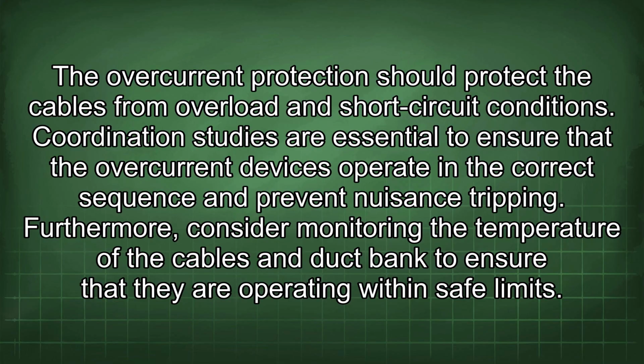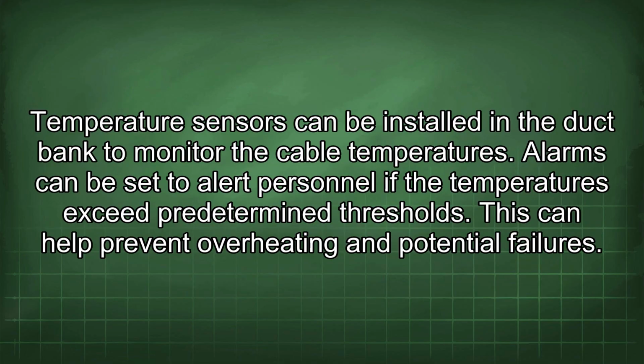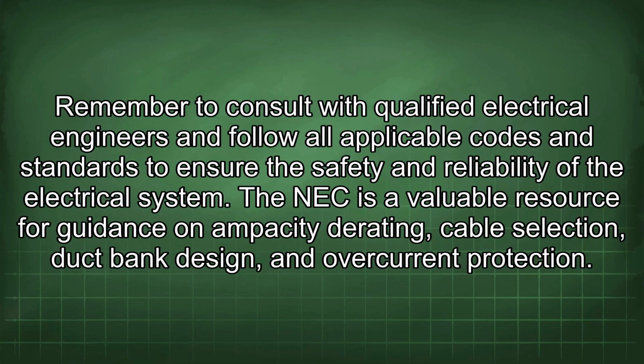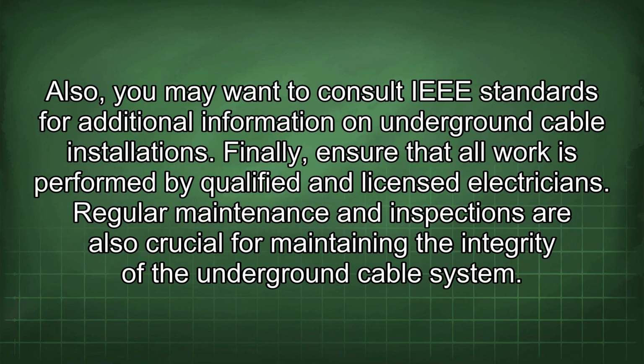Furthermore, consider monitoring the temperature of the cables and duct bank to ensure that they are operating within safe limits. Temperature sensors can be installed in the duct bank to monitor the cable temperatures. Alarms can be set to alert personnel if the temperatures exceed predetermined thresholds. This can help prevent overheating and potential failures. Remember to consult with qualified electrical engineers and follow all applicable codes and standards to ensure the safety and reliability of the electrical system. The NEC is a valuable resource for guidance on ampacity derating, cable selection, duct bank design, and overcurrent protection. Also, you may want to consult IEEE standards for additional information on underground cable installations.